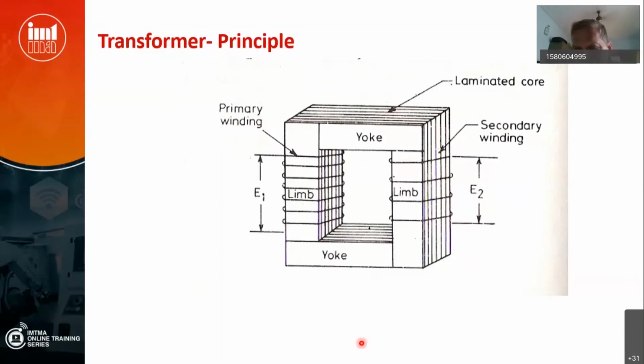Why is a transformer required in the first place? I told you that at the generating station, in most cases we generate at 11 kV, barring a few cases of maybe around 15, 20, whatever it is. We are generating at a particular voltage. To transfer a particular amount of power, maybe 10 megawatt, to the city of Bangalore from a generating station. Megawatts or watts, it is V into I. So, if I send the power at 415 volts, what is the current for that 10 megawatt? If I transmit it at 11 kV, what is the current?